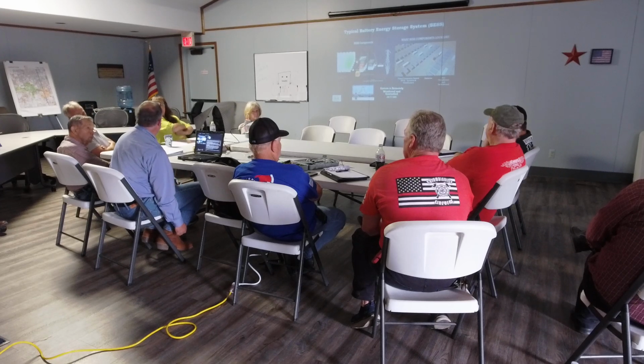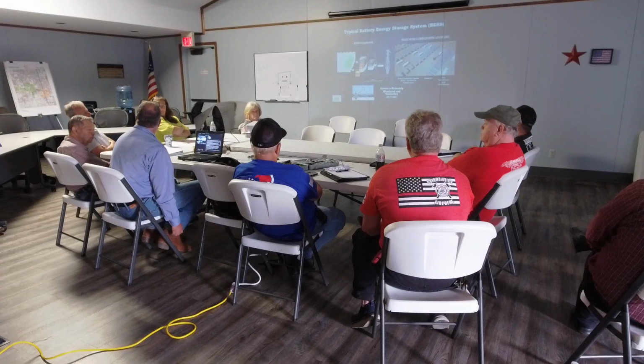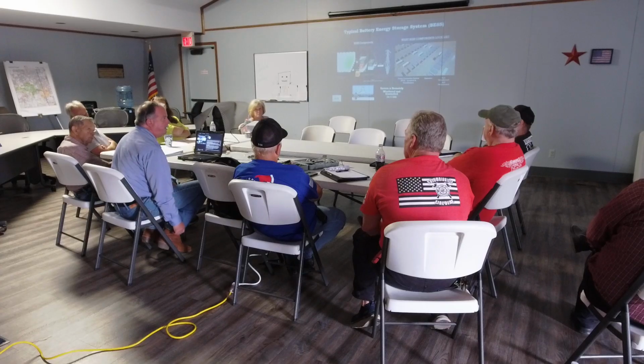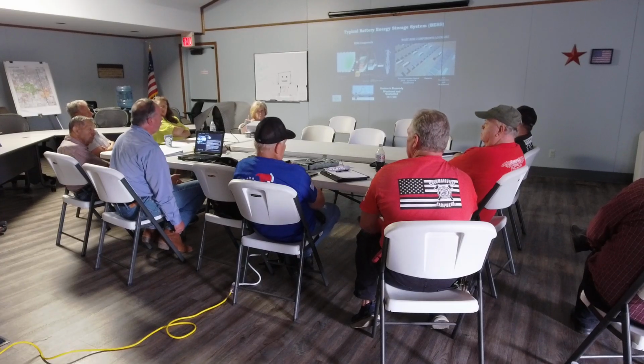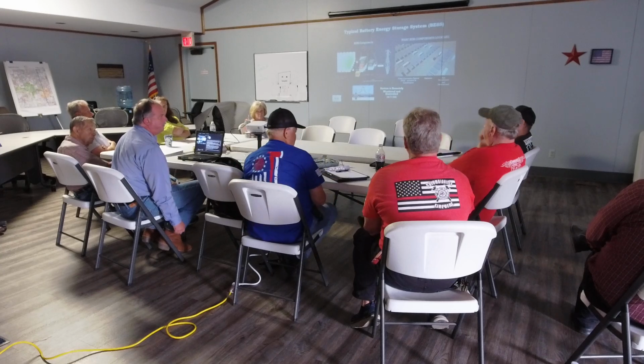That's correct, it's outside. It's very rare now to find battery storage systems for utility put inside of a building. Has anybody seen Moss Landing? That's why. NFPA 1 is a beautiful document, but unfortunately, when we put things inside of buildings where people are going to walk into, NFPA mandates sprinkler systems. Water and batteries do not mix, and that's why developers are not doing indoor installations anymore.